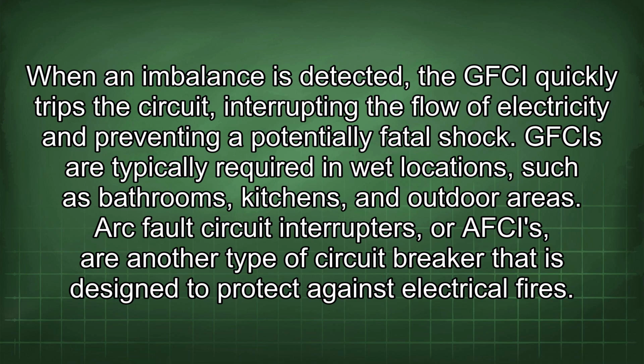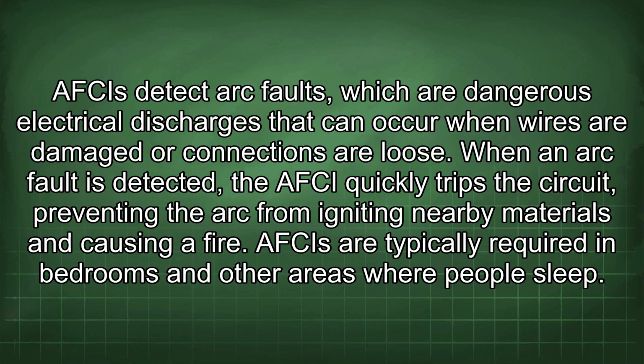Arc fault circuit interrupters, or AFCIs, are another type of circuit breaker that is designed to protect against electrical fires. AFCIs detect arc faults, which are dangerous electrical discharges that can occur when wires are damaged or connections are loose. When an arc fault is detected, the AFCI quickly trips the circuit, preventing the arc from igniting nearby materials and causing a fire. AFCIs are typically required in bedrooms and other areas where people sleep.